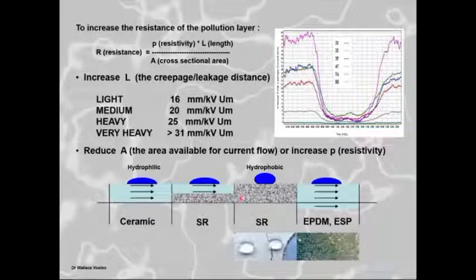Now it transfers all the way through the pollution layer to the surface of the pollution, and now it can't wet. Well, what is the area available now for current flow? Whew, it's about nothing. When that tends to nothing, that tends to infinity, so that becomes very high. So you see, that is why silicone rubber insulators work so well. You can see here's the water drop sitting on the surface, and the electrolyte is not forming. No electrolyte, low area available for current flow, big improvement in performance. So your resistance goes up, current comes down, you are happy chappy.